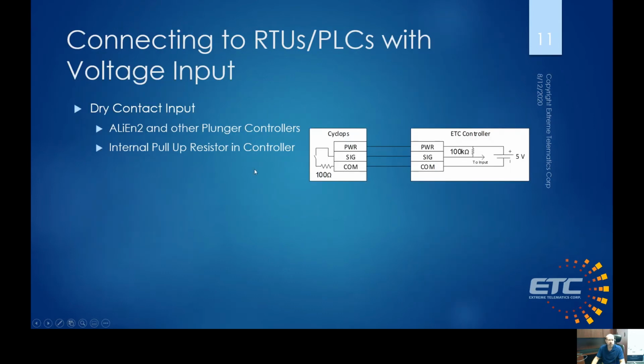Now, if you're going to use an RTU or a PLC, there are many cases where they don't have a dry contact input, like what we have in our Alien 2 plunger controller or all other plunger controllers. They have a voltage input. So the way that a dry contact input works, and this might exist on some of your RTUs and PLCs, so you want to make sure that you check that first, is there's an internal pull-up resistor on the controller side. So what happens is, when the Cyclops, which is normally open, or Sasquatch, or any plunger arrival sensor, there'll be a normally open switch.